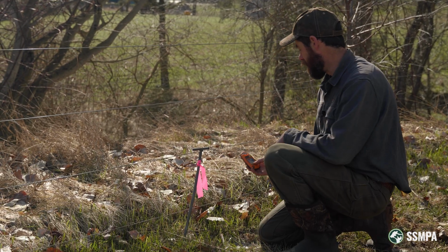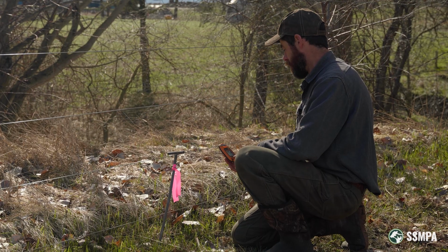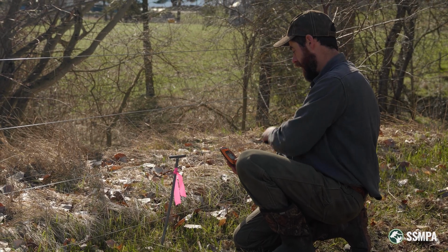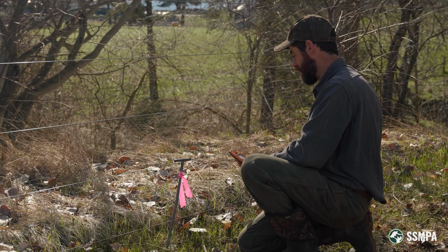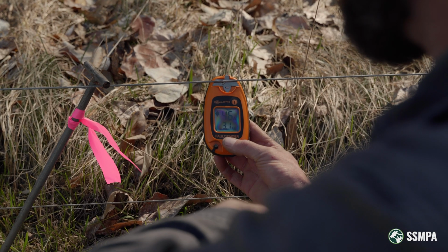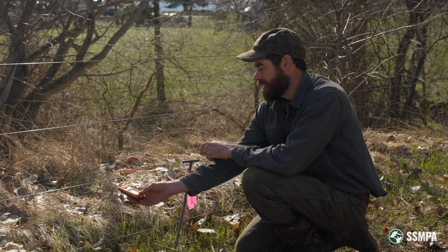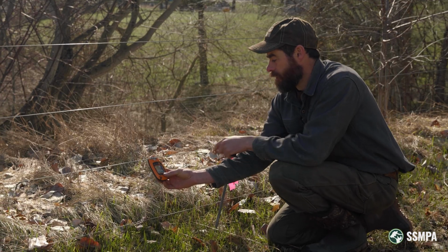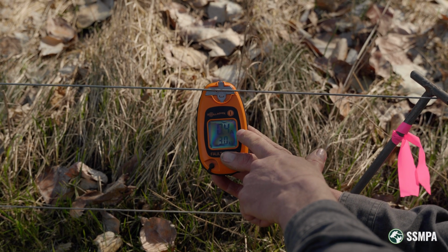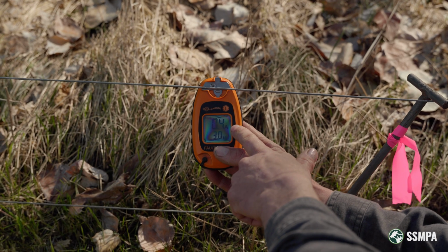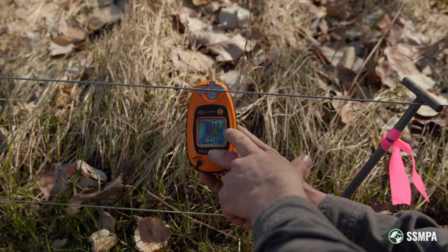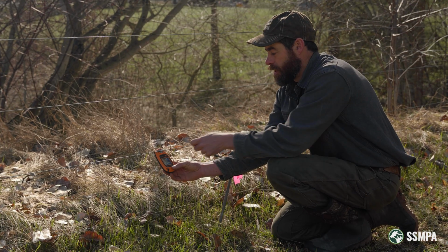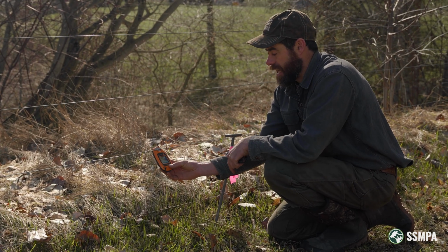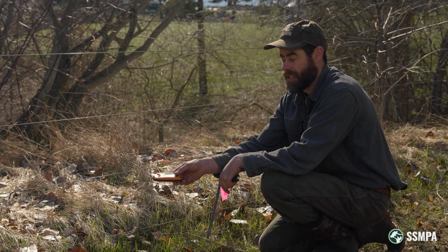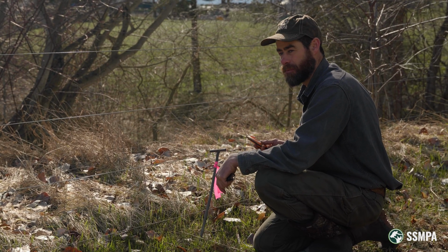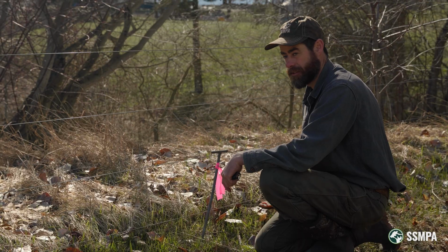So when we're on this side of our short, the Energizer's over there, and we can still see the current flowing here. We can still see our 4 amp draw with the arrow pointing this way. But as soon as we've passed the fault that we're searching for, we're still seeing a low voltage, but our amperage has dropped to almost nothing. Now there's only a 0.3 amp draw, and the arrow has also disappeared. So when you get to the point where the amperage drops substantially, you know that you've passed your fault, and you should go back toward the previous point you tested and search for what the problem is.